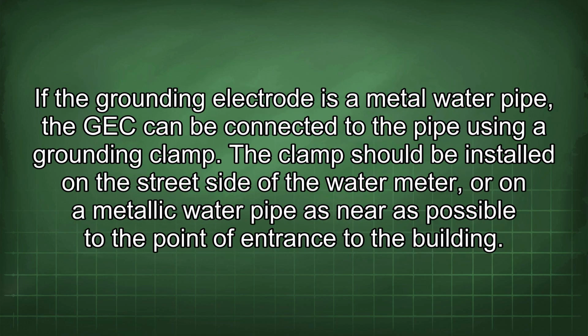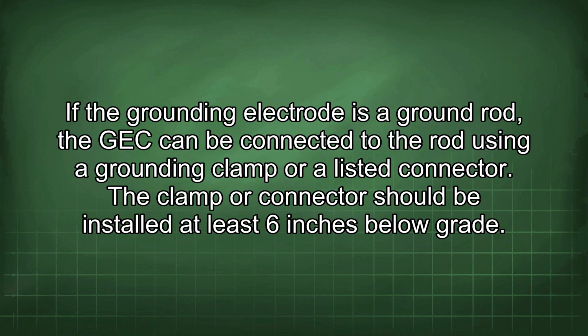If the grounding electrode is a metal water pipe, the GEC can be connected to the pipe using a grounding clamp. The clamp should be installed on the street side of the water meter, or on a metallic water pipe as near as possible to the point of entrance to the building. If the grounding electrode is a ground rod, the GEC can be connected to the rod using a grounding clamp or a listed connector. The clamp or connector should be installed at least 6 inches below grade.